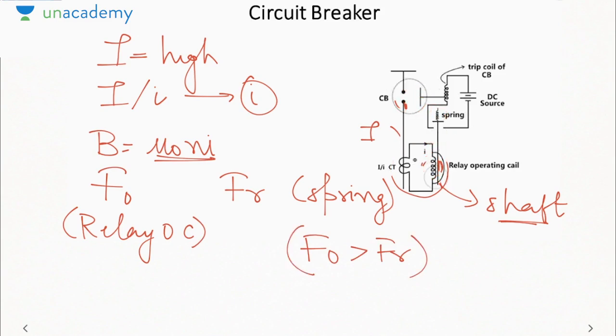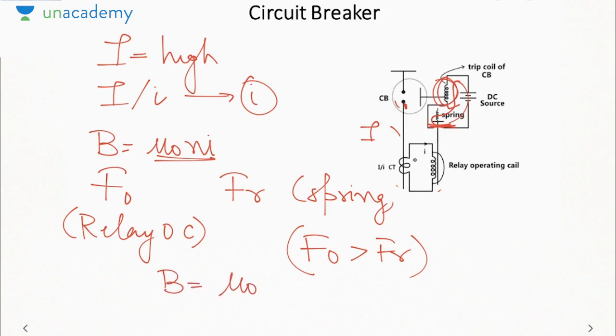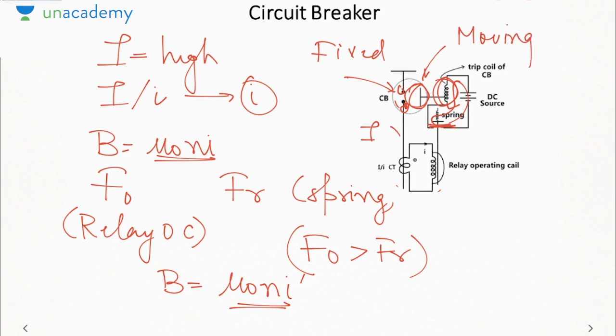Now as it is pulled down, what will happen? It will get connected here, due to which this circuit becomes closed. Now current will start to flow. Current will flow in this coil, due to which this coil experiences a magnetic field, let us say mu naught N I dash, due to which this contact will be pulled away from these 2 terminals. Hence, if you see here, in the circuit breaker we have 2 contacts. This one is called the fixed contact, the other one is called the moving contact. So that is how the relay and the circuit breaker coordinate.